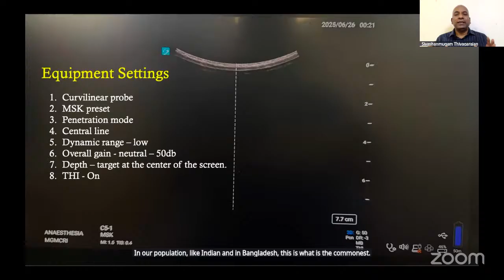Commonly, we select a musculoskeletal preset. If your machine has a spine preset, that is great. Usually, even in the low frequency probe, we try to select the lowest frequency. The curvilinear probe fires between 1 to 5 megahertz. Within that 1 to 5, we want to choose between 1 to 3 megahertz. So by choosing a penetration mode, we instruct the machine to fire between 1 to 3.